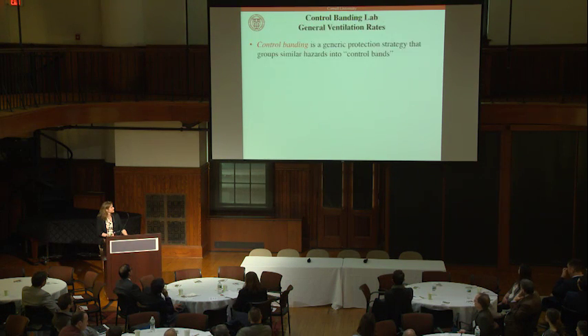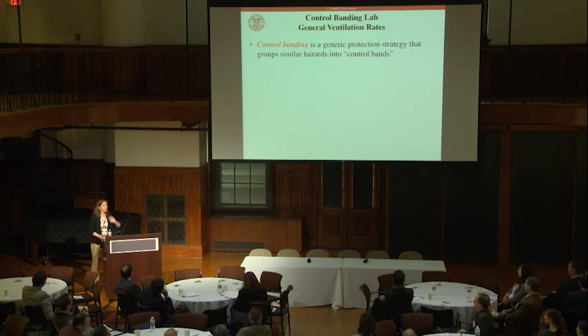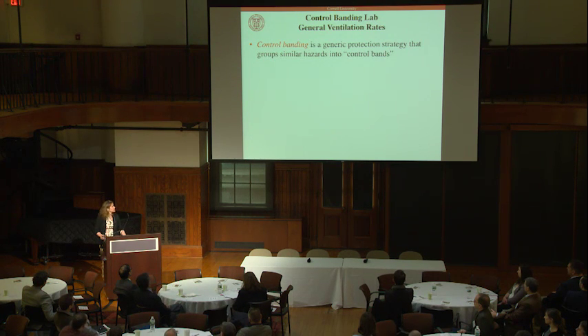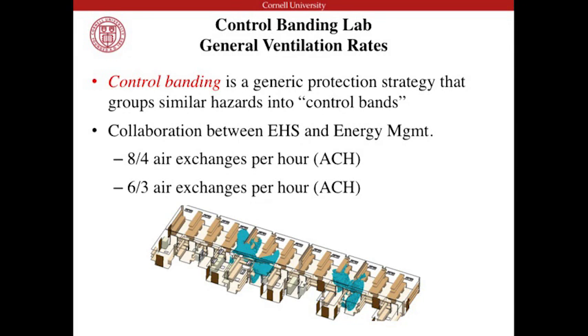A big component of the program is this control banding, the 8 and 4 air exchanges down to 6 and 3. This is a generic protection strategy where you group similar hazards into bands. Through collaboration between my office and the utilities department, we settled on 8 and 4 as a design-to standard, and we wanted to find places where we could go down.